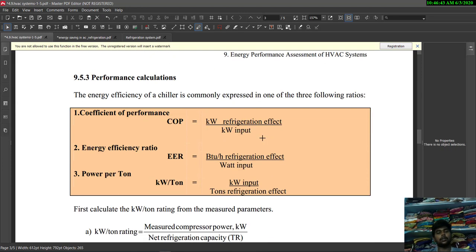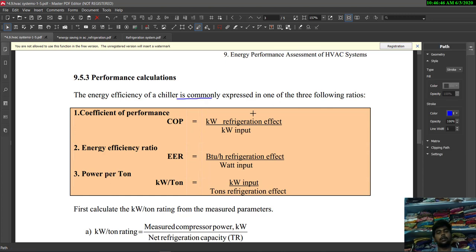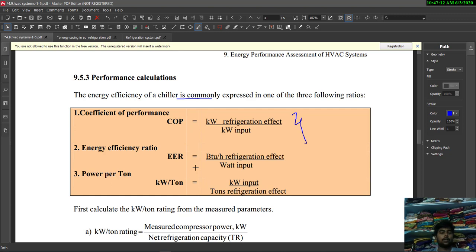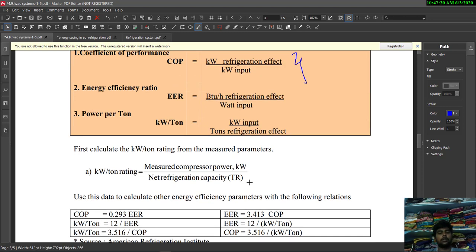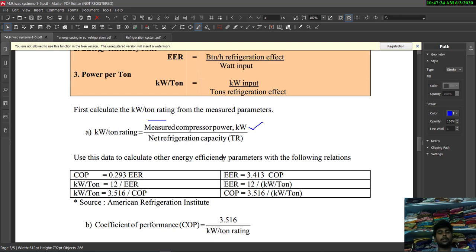Next is performance calculations. The energy efficiency of a chiller is commonly expressed in one of three ratios: first, coefficient of performance (COP) = kilowatt refrigeration effect / kilowatt input; second, energy efficiency ratio (EER) = BTU per hour refrigeration effect / watt input; third, kilowatt per ton = kilowatt input / tons of refrigeration effect. Kilowatt per ton is calculated from measured compressor power in kilowatt divided by net refrigeration capacity in tons.